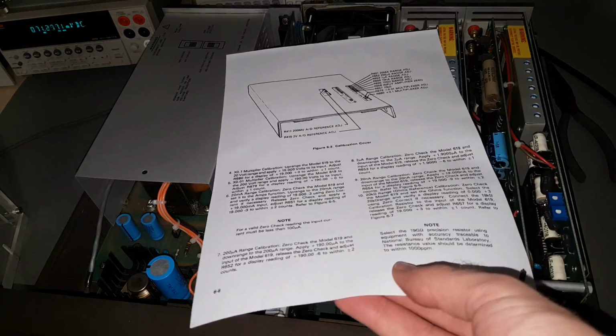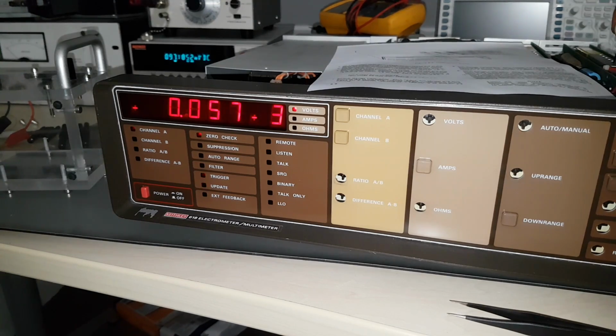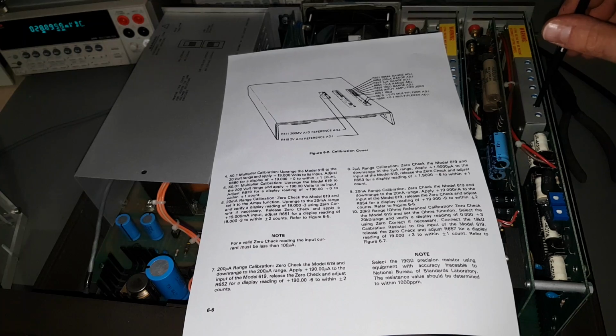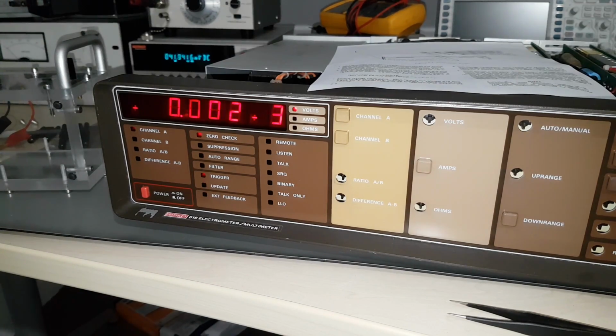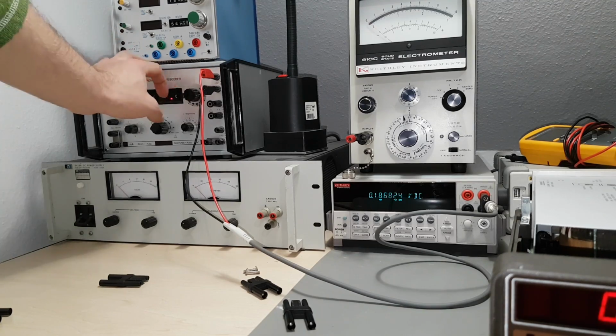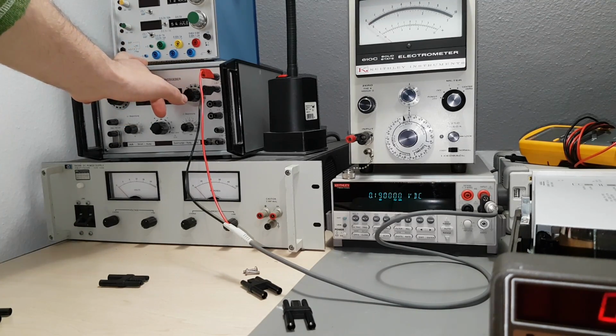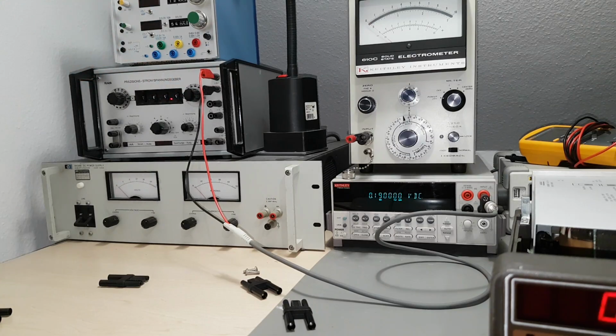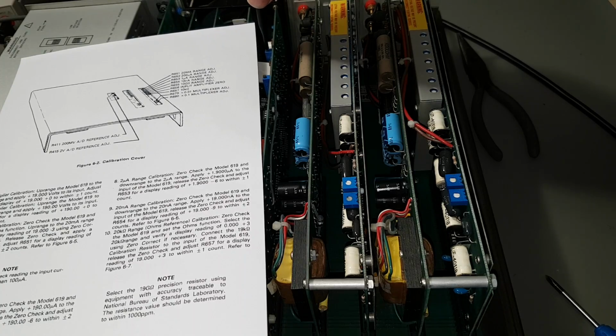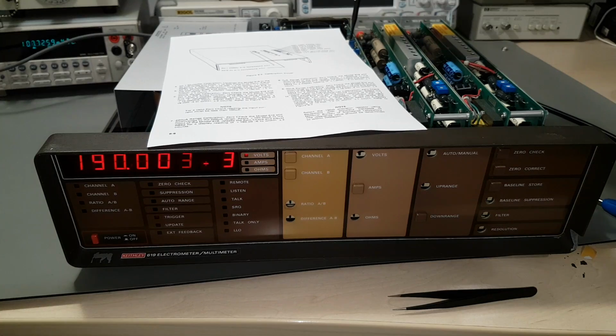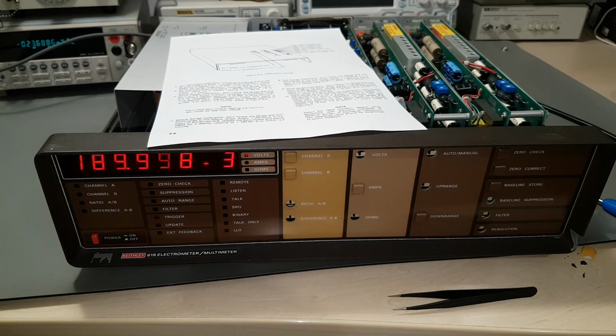Then, after some time has passed, we can start with adjustment number 1, input amplifier 0. In the most sensitive voltage range, with 0 check engaged, we'll adjust the appropriate potentiometer until 0 is displayed. Next, we'll adjust the ADC reference voltages by applying 190 mV and 1.9 V to the electrometer input and adjusting the appropriate potentiometers until those values are displayed as correctly as possible. That scheme is repeated for the following 19 steps, with slight variations. I'll save some time and spare you the video documentation of those.